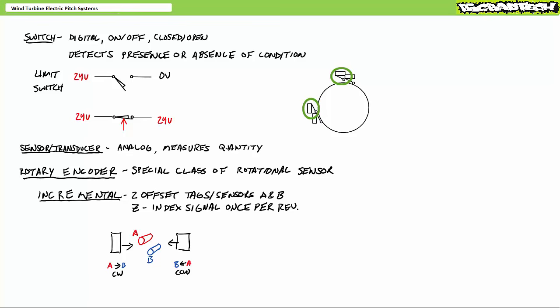Often a turbine making use of electrically pitched blades prior to actually pitching them will purposely rotate the blades in one direction and then the next until it strikes 90 and then 0, establishing the upper and lower bounds and setting them as reference. From these references, absolute angles can be determined. If it takes 200 turns to go from 90 to 0, 100 turns is 45 degrees, and so on.